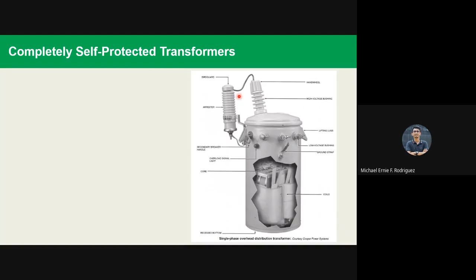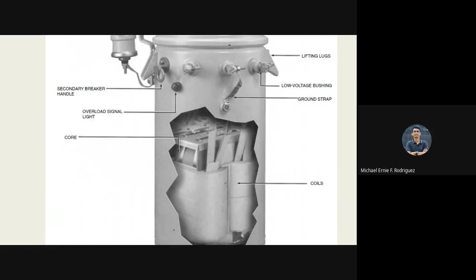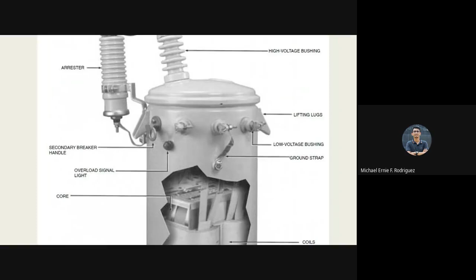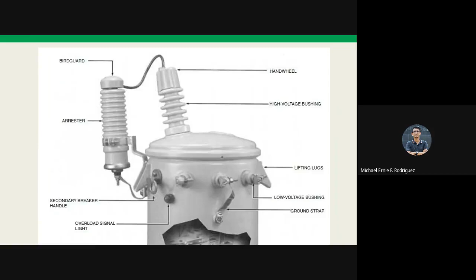And then kung mapansin ninyo, meron tayong overload signal light. So kasama to sa mga CSP transformers, meron ka nang overload signal light. Meron ka na rin breaker, okay, arrestor, ayan. So for CSP, in the CSP transformer, primary fuse is situated within the case. Because its characteristics are different from those of the external primary fuse, meron ka pa kasing external primary fuse. So ang tawag sa external primary fuse, that is the weak link. Okay.